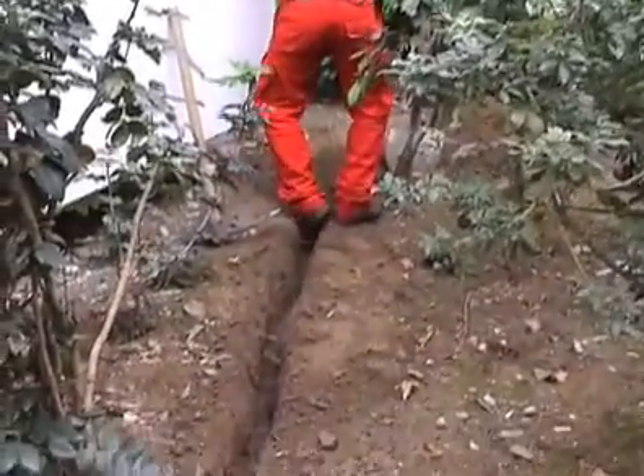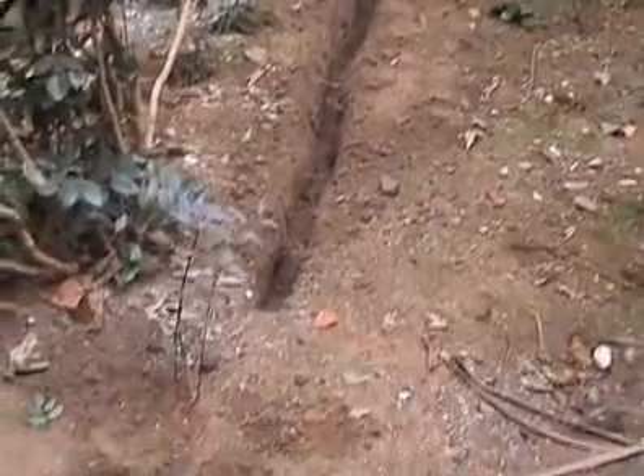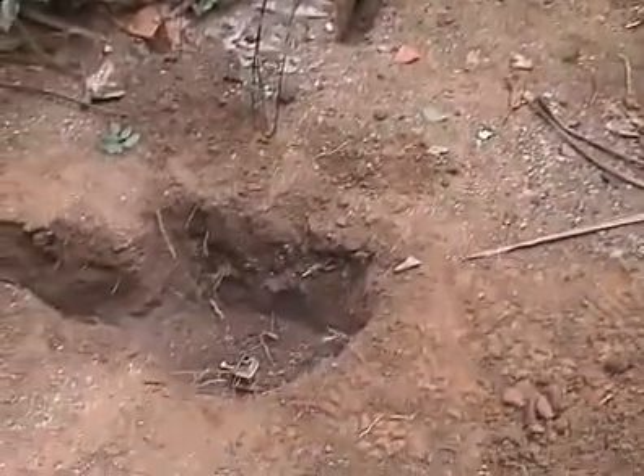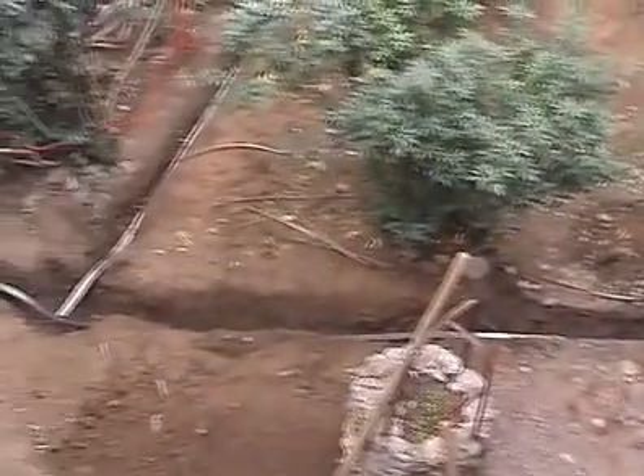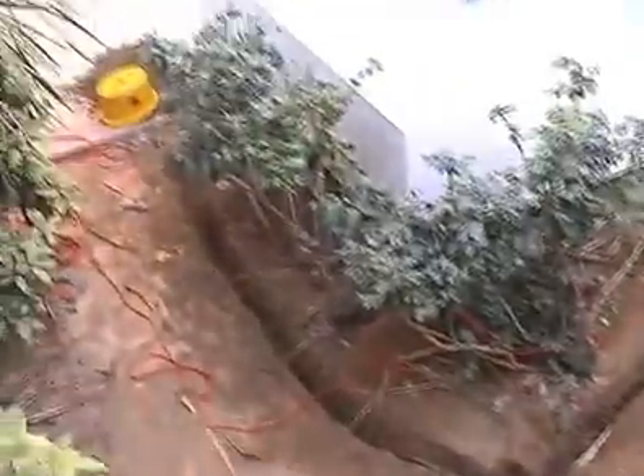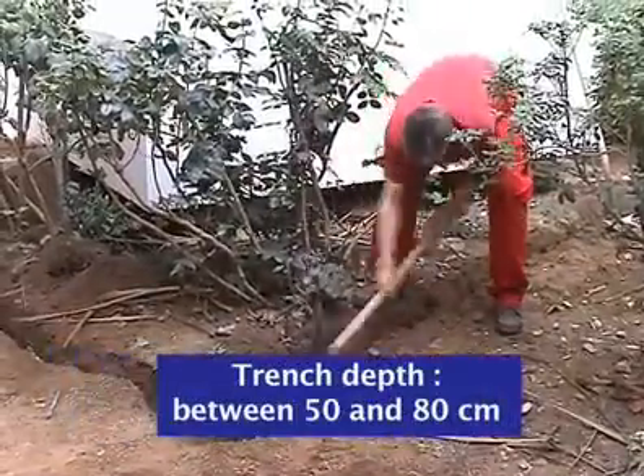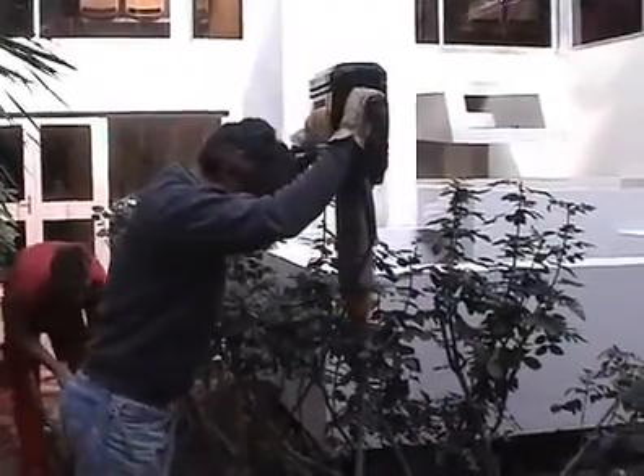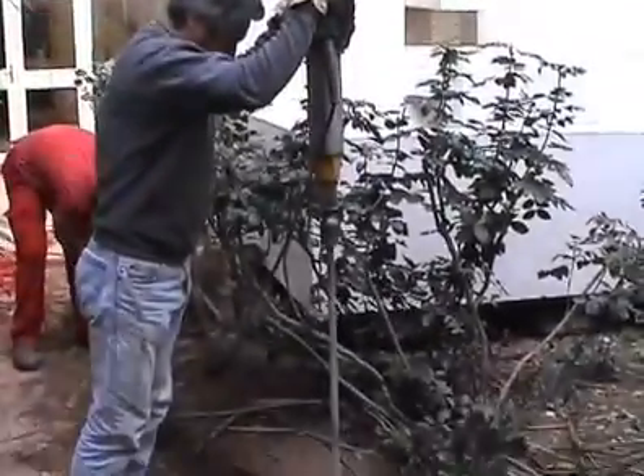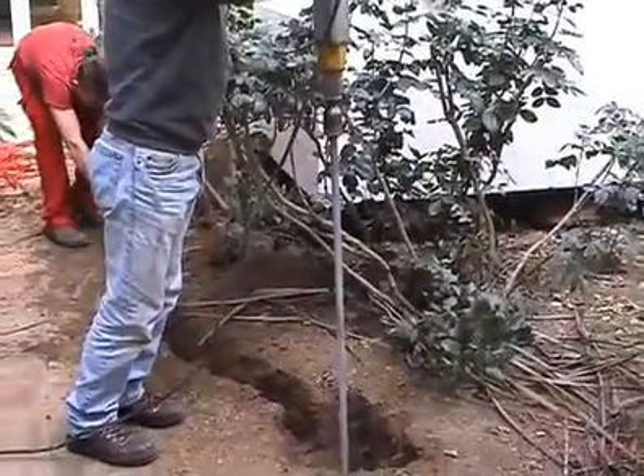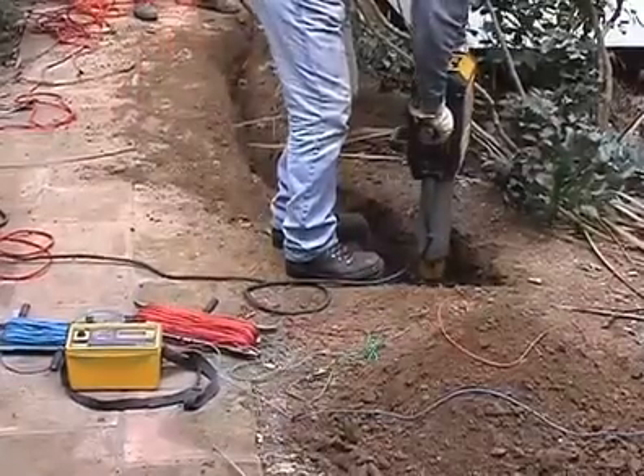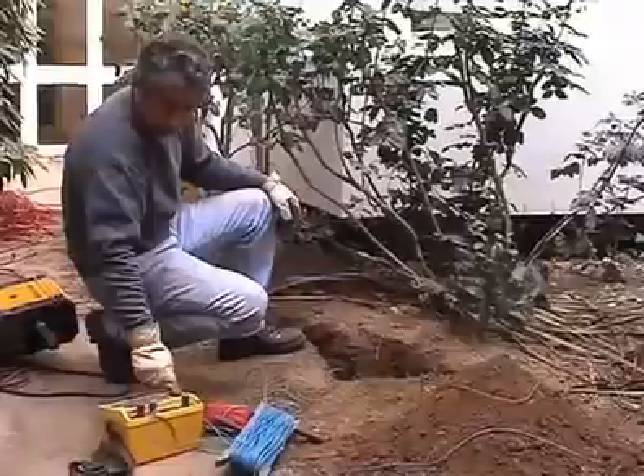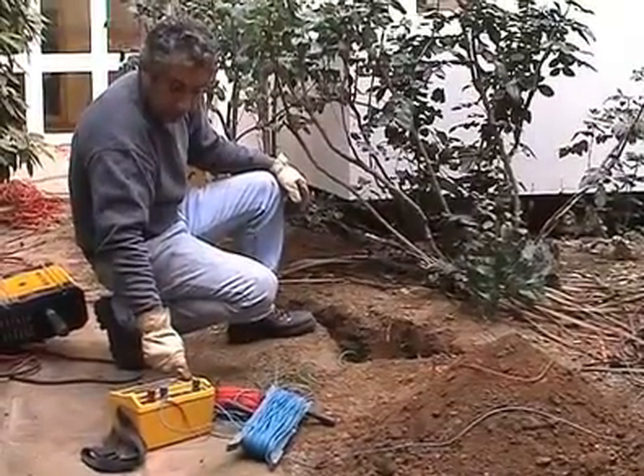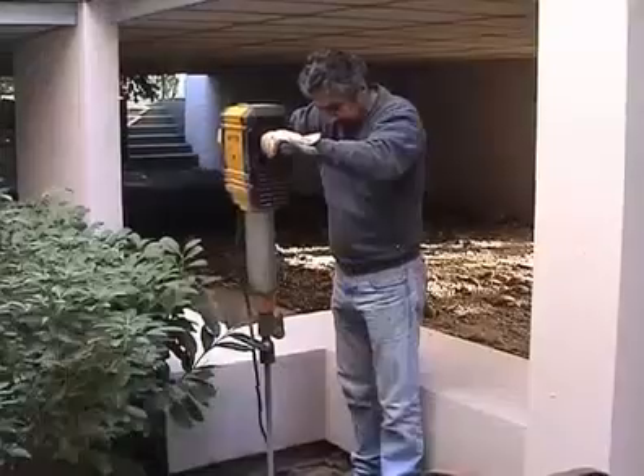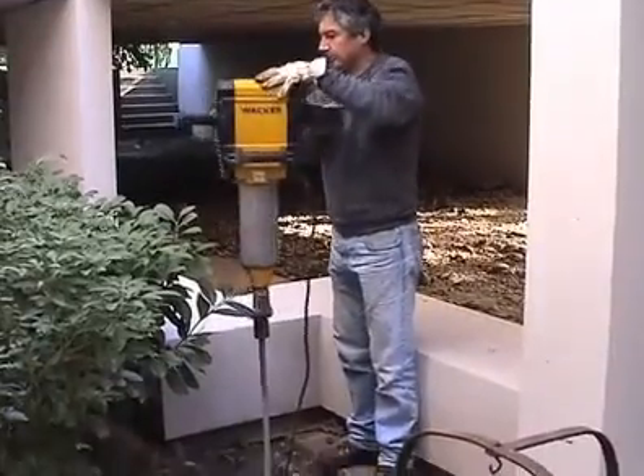Trench should be as narrow as possible in order not to change the initial structure of the ground too much. Its depth should be at least 50 centimeters to keep it away from frost, but not too deep as the lightning current dissipates better in the ground surface. The first rod is placed 3 meters away from the building, as it is constructed out of 3 elements of 1 meter each.